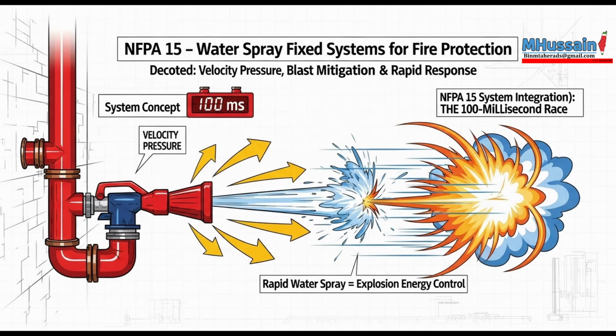Yeah. Okay, let's shift gears to that fifth hazard category: vapor mitigation, section 7.5. What's the goal here? The main objective is using water spray to deal with a vapor cloud before it ignites. You want to dilute it, disperse it, or maybe absorb it to get the concentration below the lower flammable limit, the LFL. That's from 8.7.5.